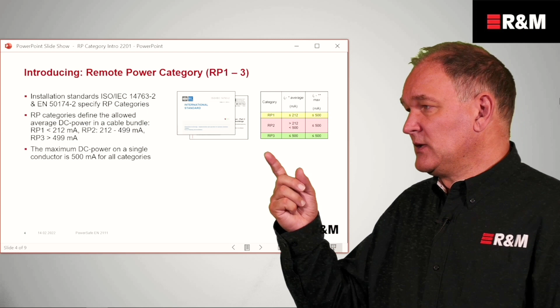Here we have to keep in mind, we talked before on slide 2 about the current per pair. Here we're talking about current per wire, so obviously one wire is half of a pair. And 500 milliamps here for RP3 is the same as the 1 amp that we have for 4-pair PoE. The way RP1 was defined, 212 milliamps is the level of current that is considered to be allowed without having any impact on the cabling. So up to 212 milliamps on average in a bundle is considered not to increase temperature to an extent that you would have to calculate with it and consider it in the overall planning.